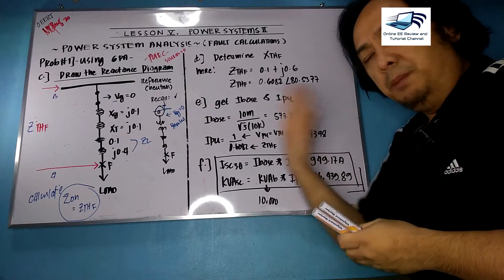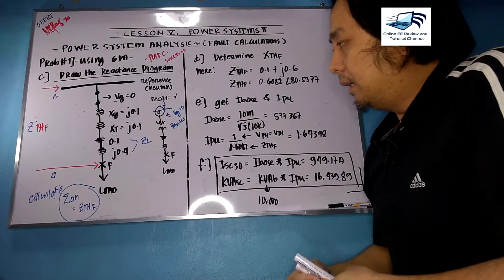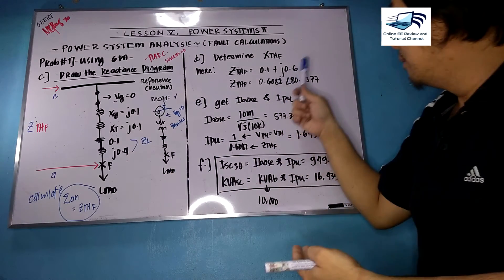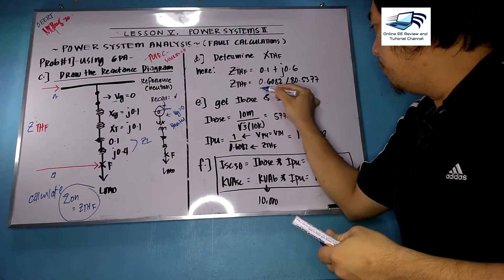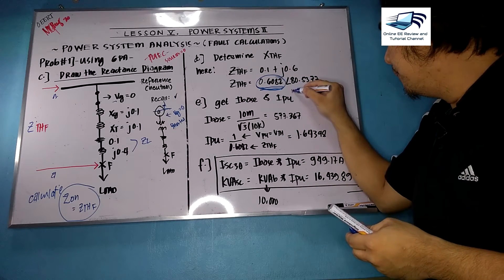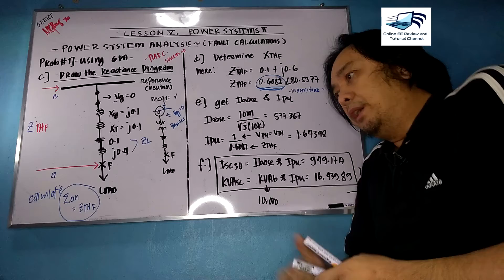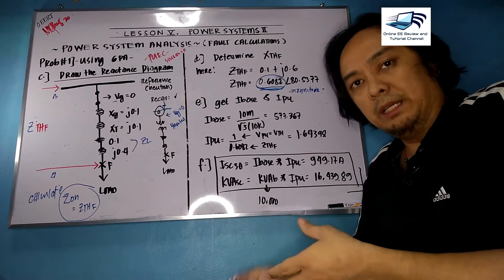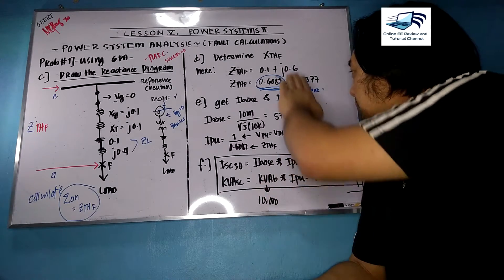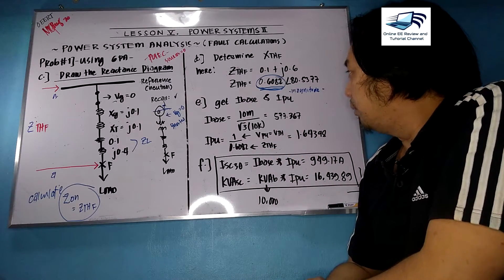We need to determine the Thevenin impedance by adding all impedances in series: j0.1 (generator) + j0.1 (transformer) + 0.1 + j0.4 (line) = 0.1 + j0.6, which in polar form has a magnitude of 0.6082. Our main goal is the magnitude for fault current calculations, though phase angles are useful for further analysis. We then proceed to get I-base and I-PU using standard equations.